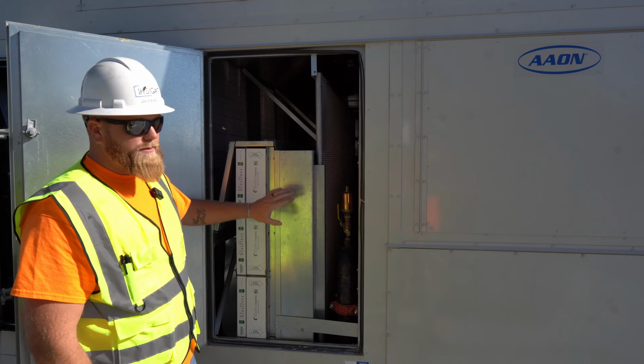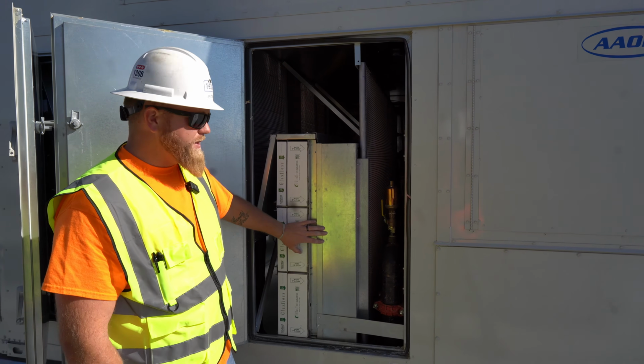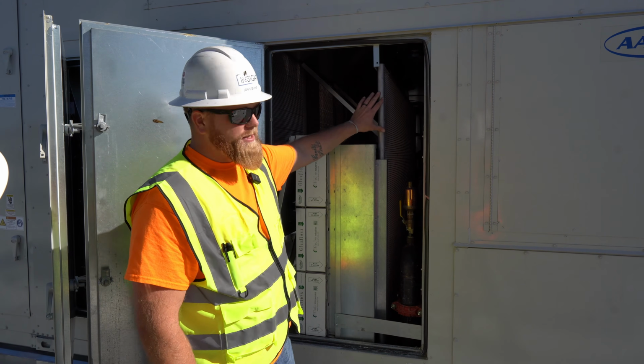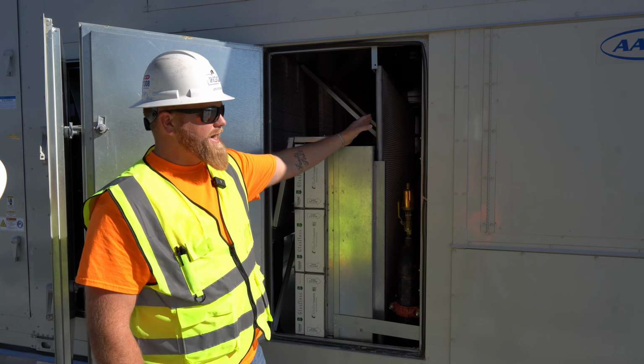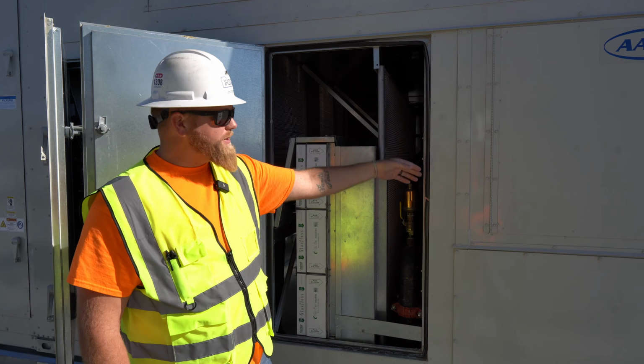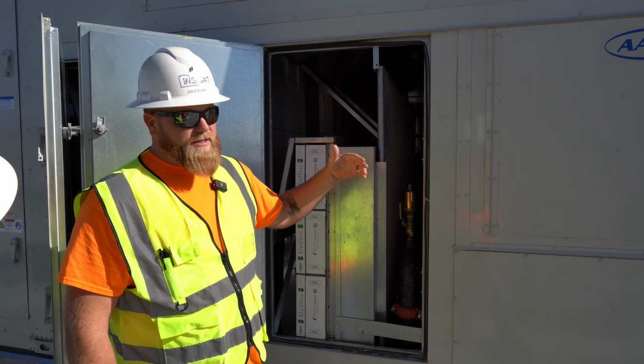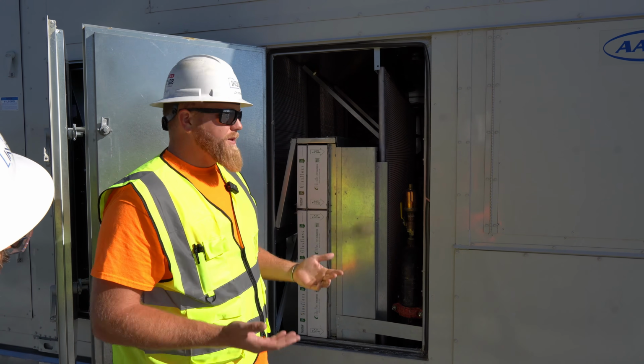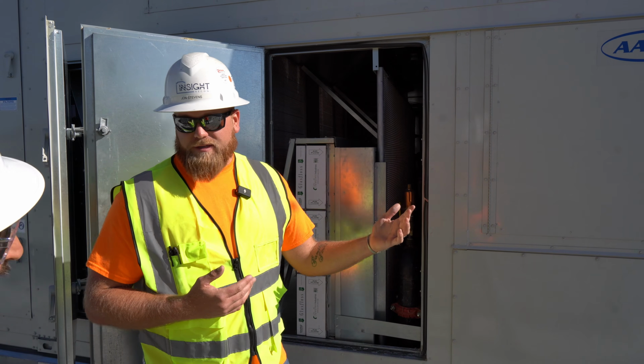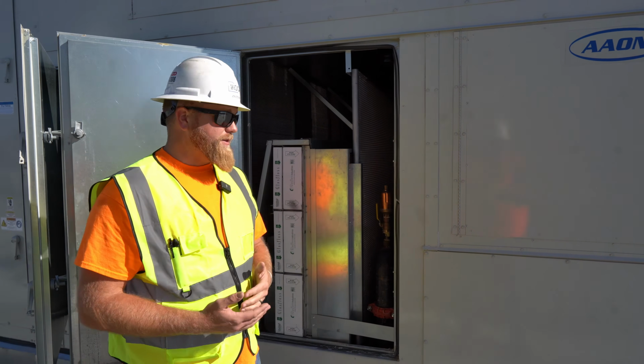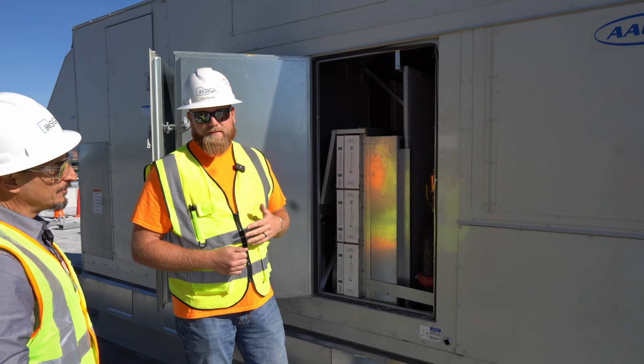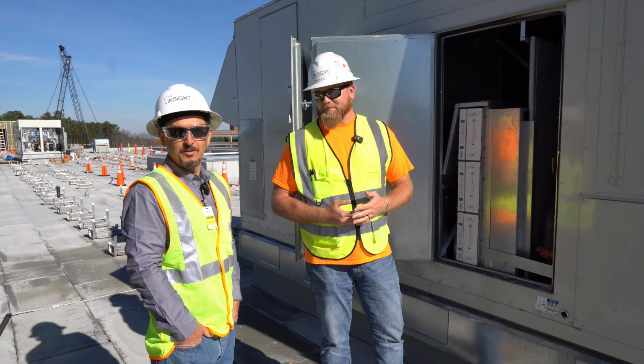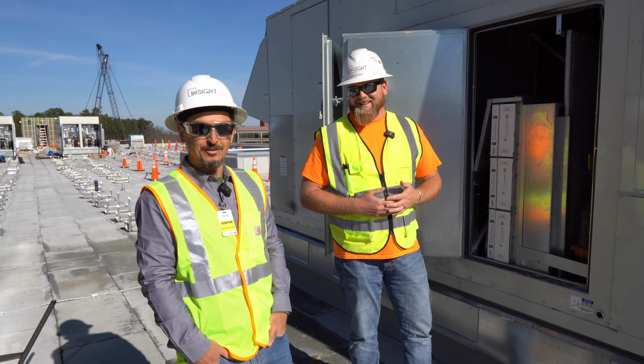So as we're going through the dehumidification, saturating all of the air through the cooling coil, this will be our single stage reheat coil. So we'll be using hot gas discharge off of the compressors. Energy consumption savings, along with utilizing the ability to reheat the air before we discharge it down into the space, to get that full psychrometrics feel out of the dehumidification. I love that. Sensible side delivering psychrometrics to the air. That could be our tagline, the full psychrometric experience.